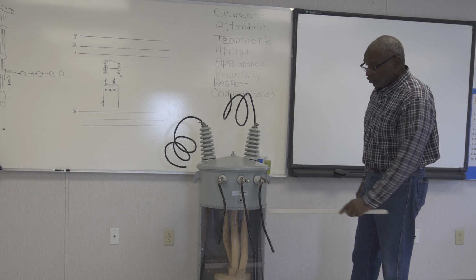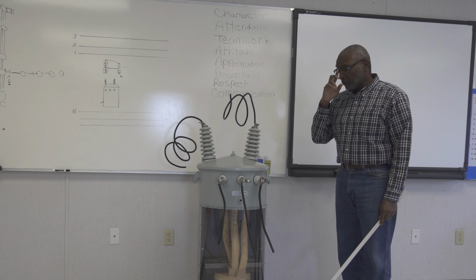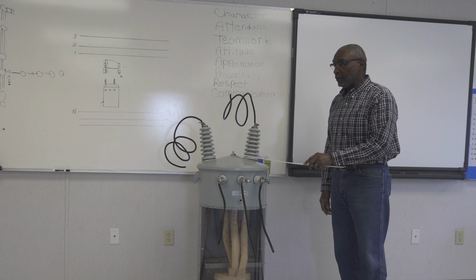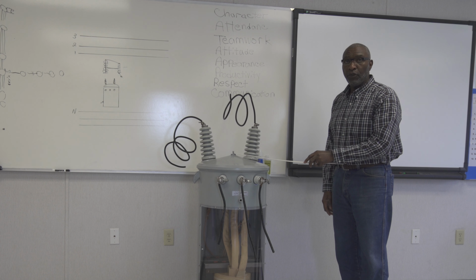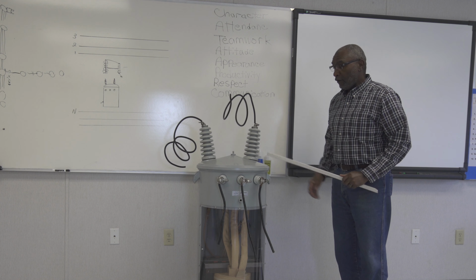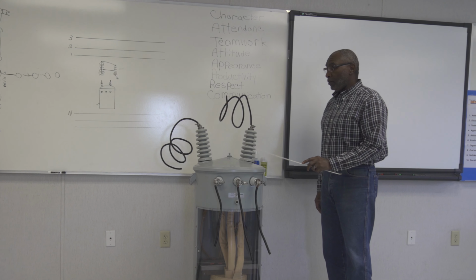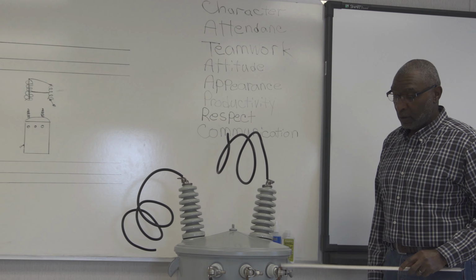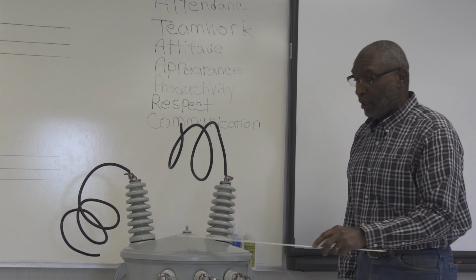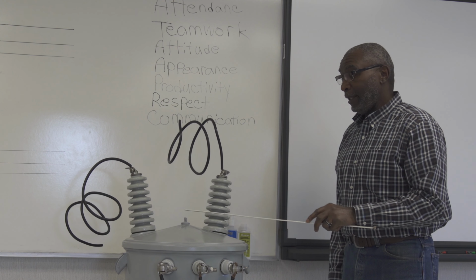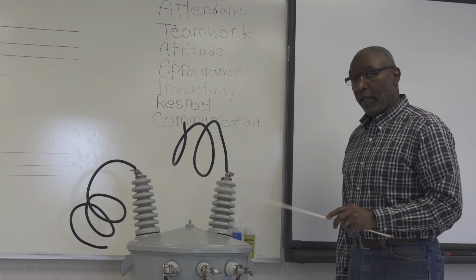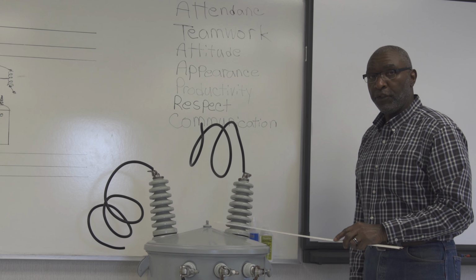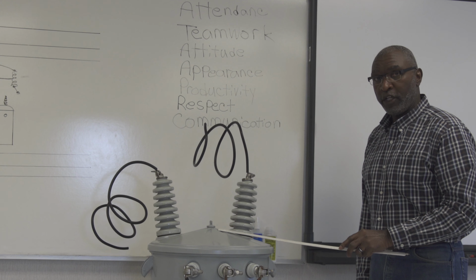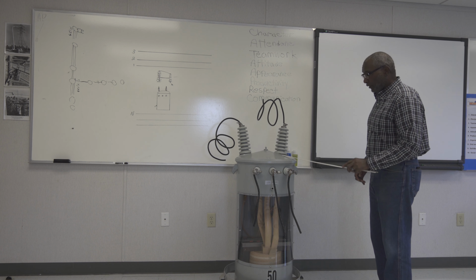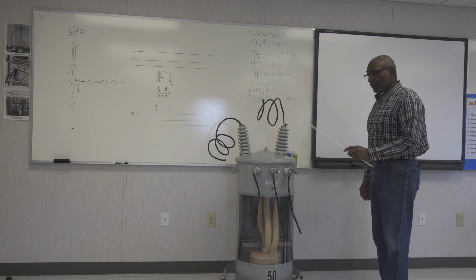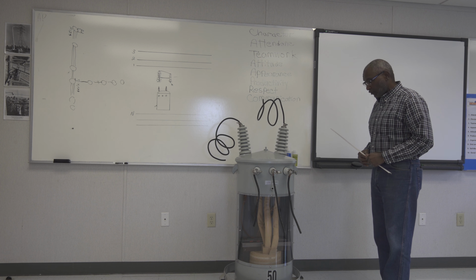If you had to go inside this transformer, which you will have occasion to do so, on this particular transformer, this wing nut here is how you will be able to take the top off. Another important step when you are going to go inside the transformer, because depending on what makeups you're doing here, you would have to go in and change the windings, and that's how you get inside the transformer. Very important that you pull that bleeder before you take this top off, because it will be some pressure on it. Overall, 50 kVA transformer for 7,200 system voltage or 14.4 system voltage.